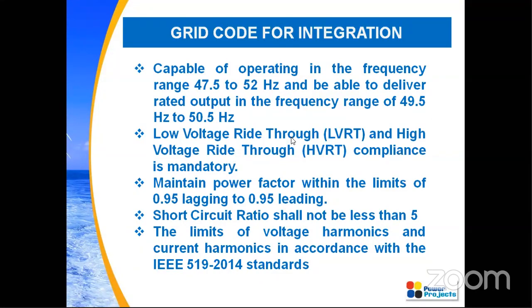Low voltage ride through and high voltage ride through compliance is mandatory. I will tell this in detail. It is also mandatory to maintain the power factor within the limits, that is 0.95 lagging to 0.95 leading. Very important thing. This depends on the reactive power support needed, so accordingly reactive power support should be there. And you have to maintain a power factor of 0.95 lagging to 0.95 leading.